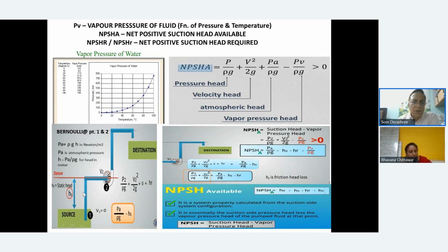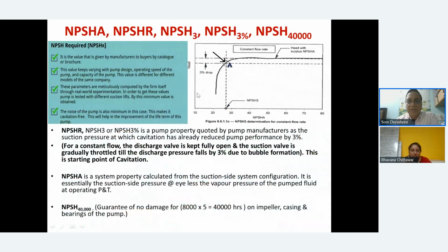Now at the suction valve, he'll start throttling. So once he throttles, of course, the pressure is getting reduced here at the eye of the pump. The moment it gets reduced, if the discharge head falls by 3%, this is what it is saying, the NPSH head required. So wherever the head falls by 3%, that is the point at which, yes, some vapors have started forming, but it's not the point of cavitation. So this is the point which is called NPSH 3 or NPSH required. Below this, cavitation is bound to happen. So that is where they use this terminology, NPSH 3 or NPSH 3%, if you come across.